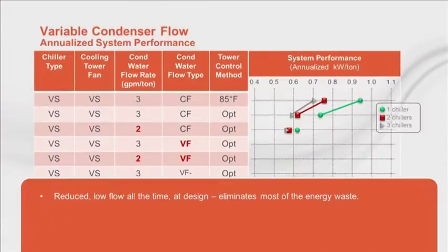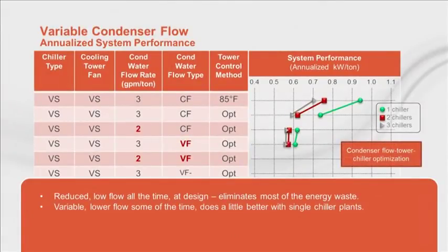Now let's vary the speed of the condenser water pumps of a system using the older 3 GPM per ton design flow rate. This could be a retrofit scenario reusing existing chillers. Now there are some savings due to proper control of the VSD, but the system performance is very similar to a system designed with reduced, constant condenser water flow. The final option is to keep with the lower condenser water flow rate and optimize the condenser water pump control. Reduce the flow further when possible. As expected, the system performance improved, but only a little bit.